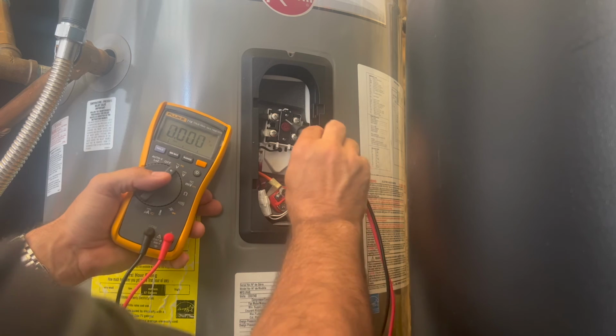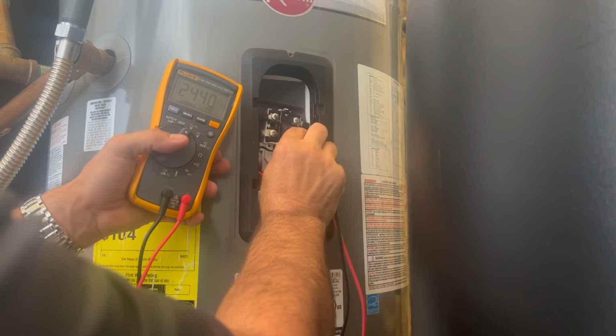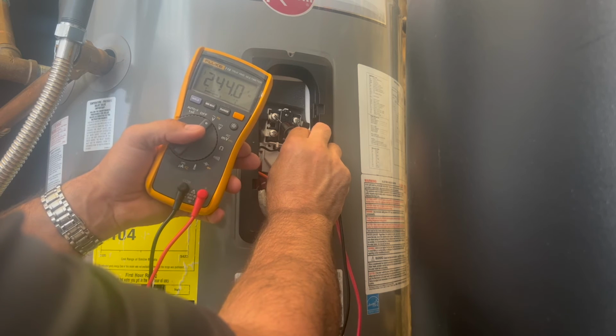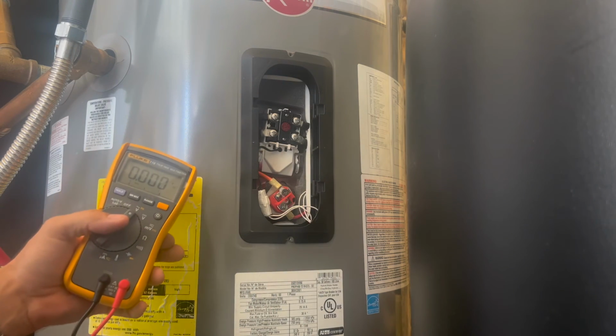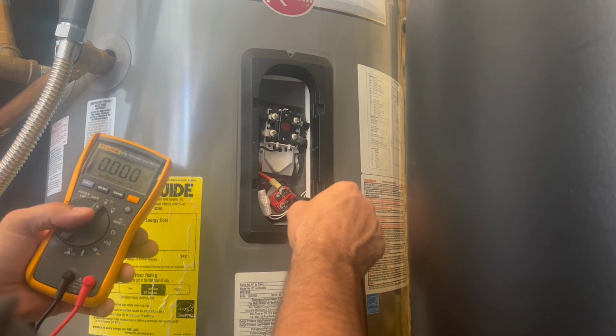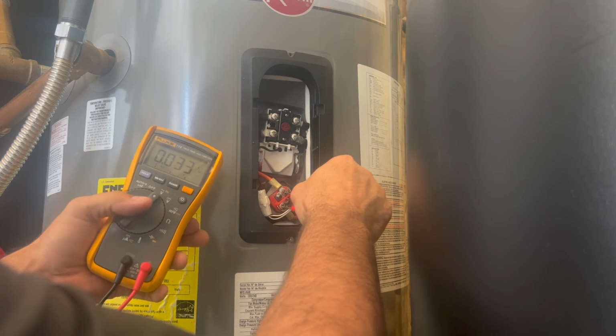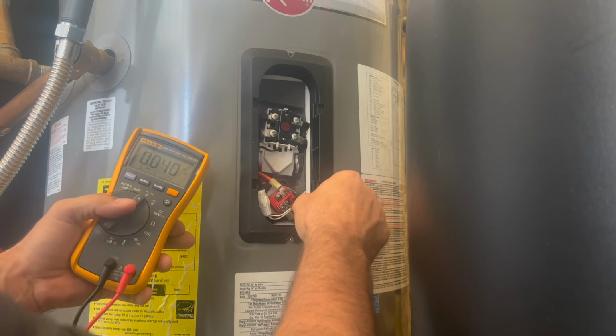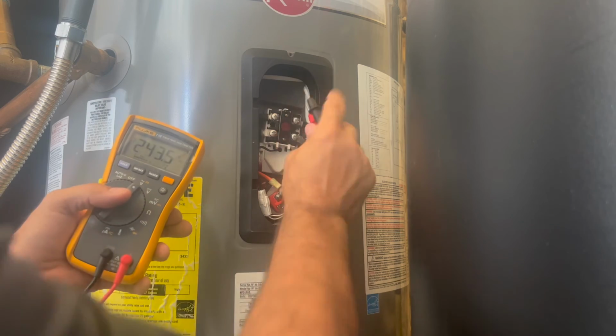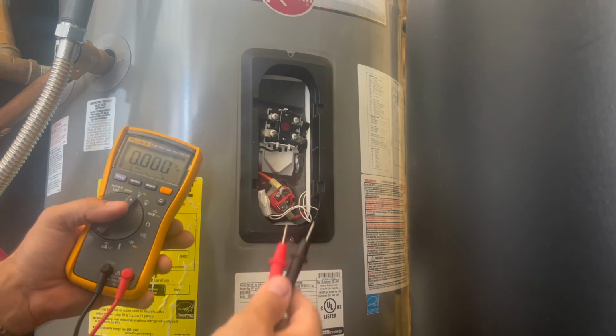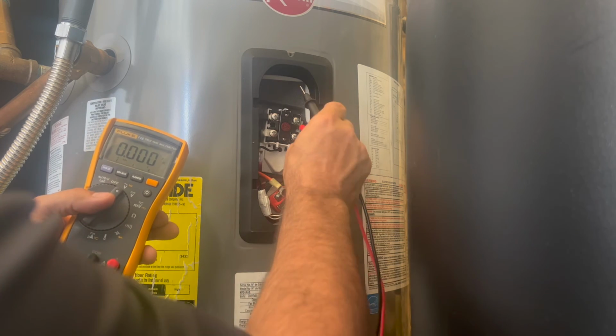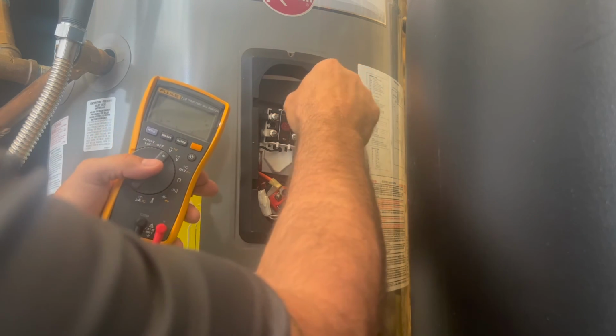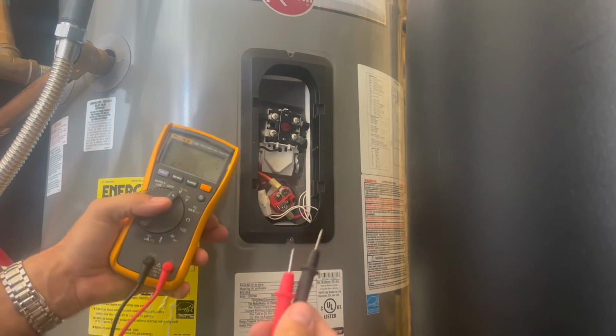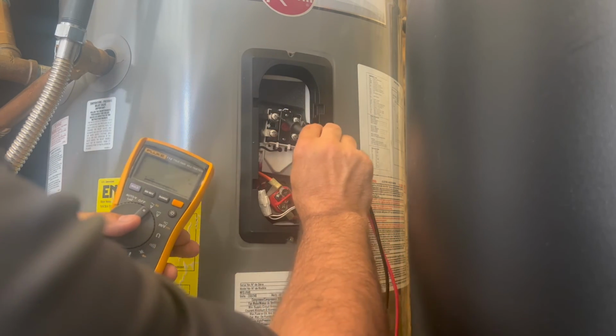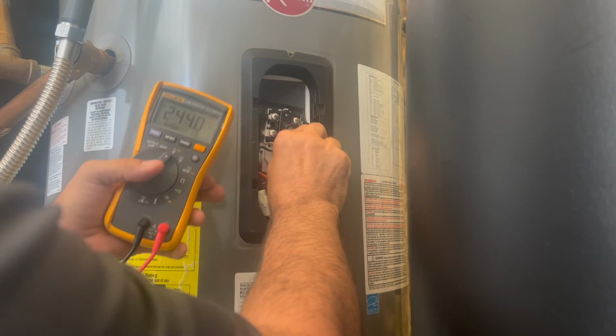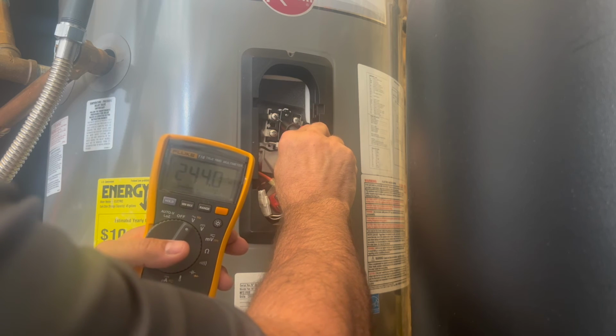This element is not activated right now. Okay? If it's activated, I'm going to touch each screw and I'm going to get a reading just like this. And the same is true for the bottom element. Okay? Only one of these will fire at a time. And you've got to make sure you've got proper voltage to the element. And that's by testing both screws, both connections, both wires up top would have been the same way. If I had a dead leg or a blown fuse or something, I could test one side and get 120 and then test the other side and get 120 and think that I'm good, think that I've got 240, but I don't. I have to do this. One on each screw, combined 240. That's what we want to see.